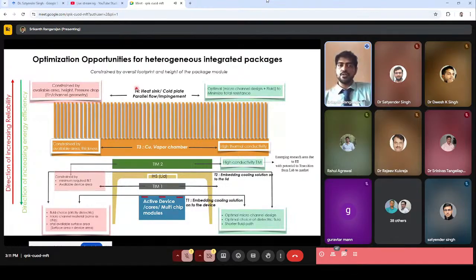From technology 4's viewpoint, you have a much bigger area and can use liquid water, so from a heat transfer perspective it seems very attractive. But the problem is there's a series of resistances between the active device and the cooling solution, so temperature can rise even before heat reaches the cold plate. First-principles calculations help decide which technology to use, but all these technologies are currently used for different applications.